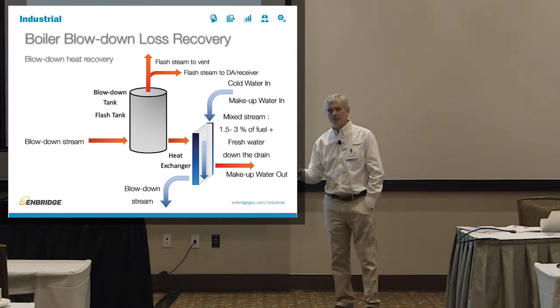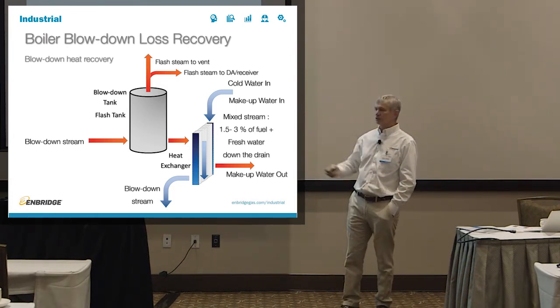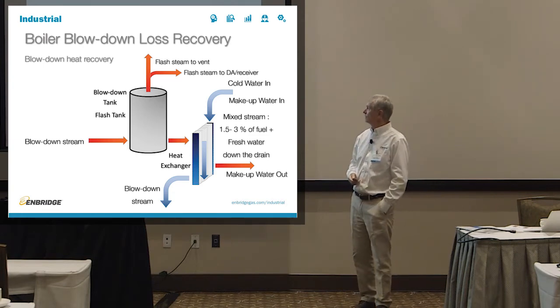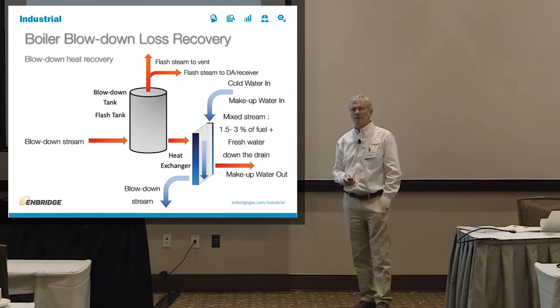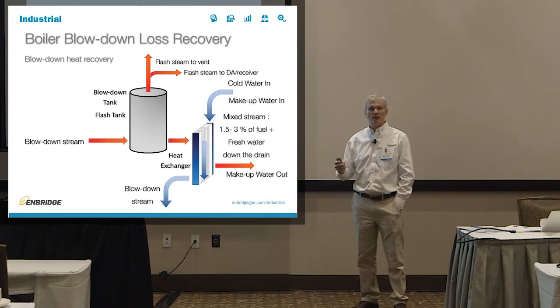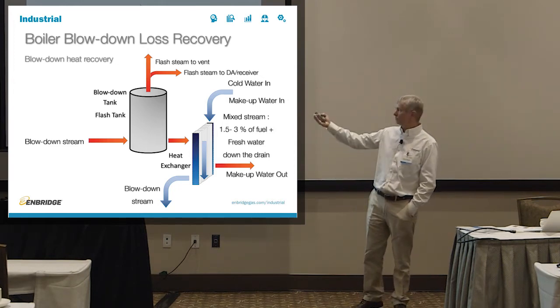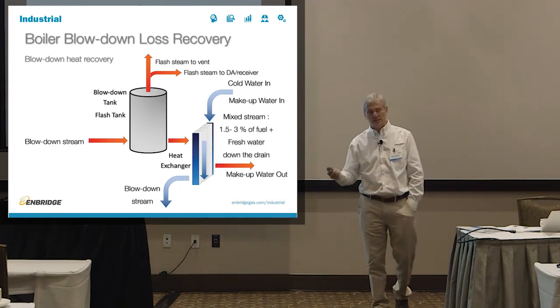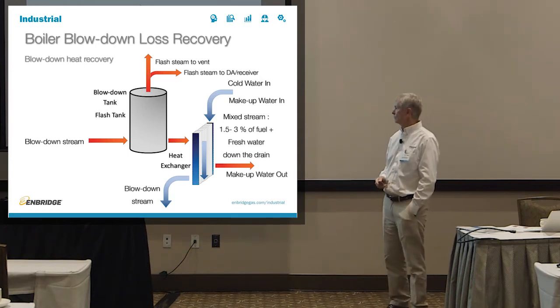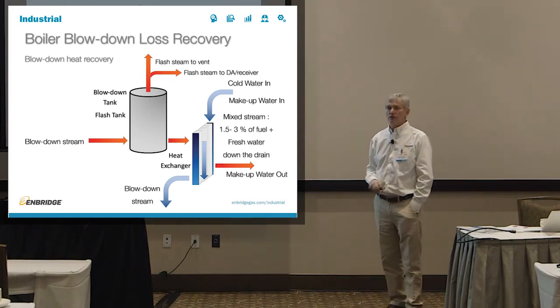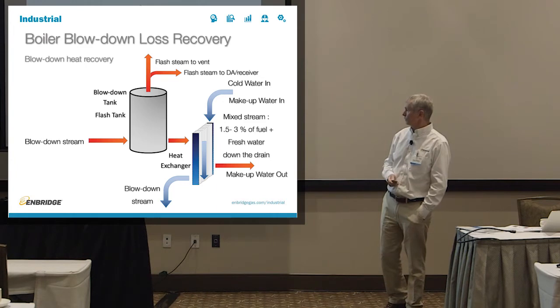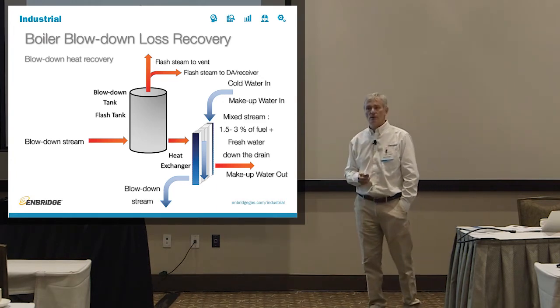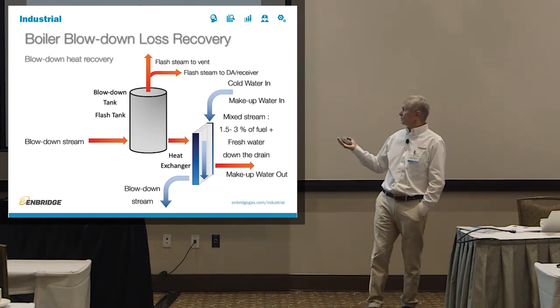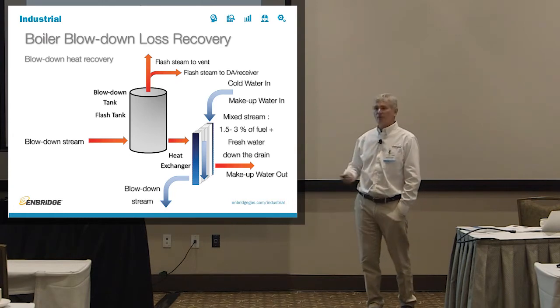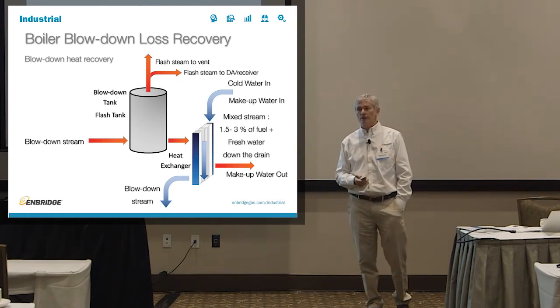In a typical application, you put the blowdown stream into some sort of blowdown tank. You vent the flash steam that is created when it goes from the boiler at 100 psi to the blowdown tank at some lower temperature. And then you drain the rest of it out into your drain by adding cold water in. That's it. So you get 3% of fuel and fresh water going down the drain, literally.